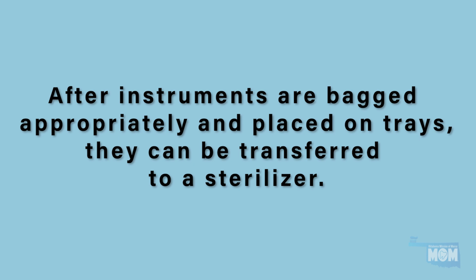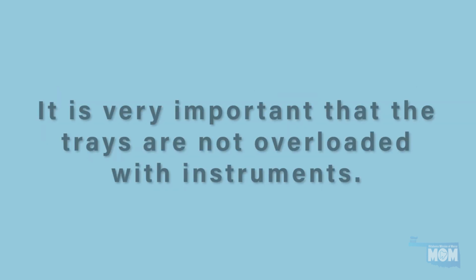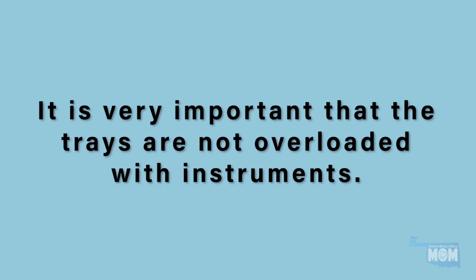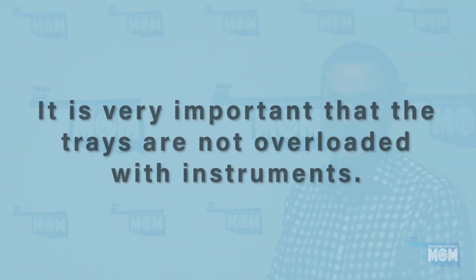After instruments are bagged appropriately and placed on trays, they can be transferred to a sterilizer. Please note it is very important that the trays are not overloaded with instruments. This may cause bags to stick together, cassettes to melt, and overheating of the sterilizer itself. If this occurs, instruments should be moved to another sterilizer and the overheated unit should not be used until ADCF staff has had a chance to examine it.